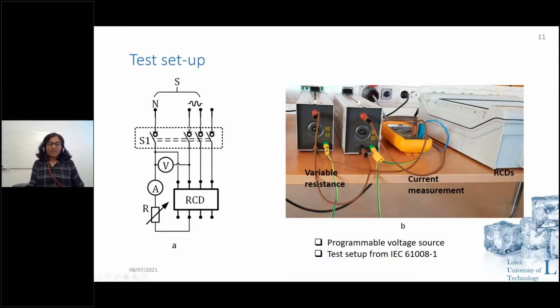This is the test setup recommended in IEC 61008, the schematic which is shown. In this schematic, we used a programmable voltage source, a waveform generator, and an amplifier. With the help of the waveform generator and amplifier, we used a voltage source to supply the RCDs. As you can see, the input to the RCD is through both phase and neutral, but the output is only through the phase, through a variable resistor, and back to neutral. So the RCD sees an unbalance between phase and neutral, and it would trip. You change the value of this resistance, and thereby the leakage current flowing through the RCD, and we can see where it trips.